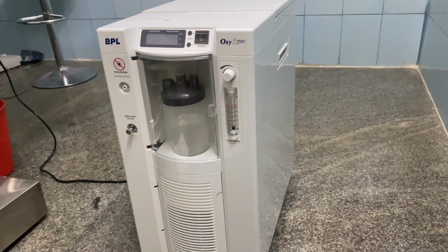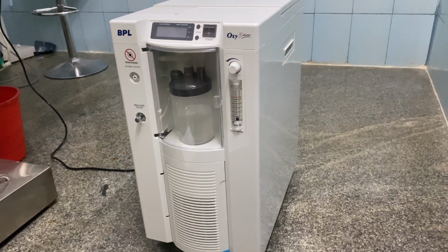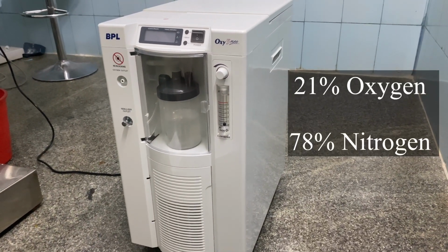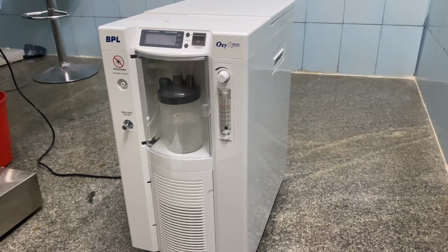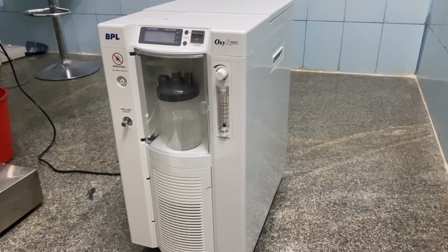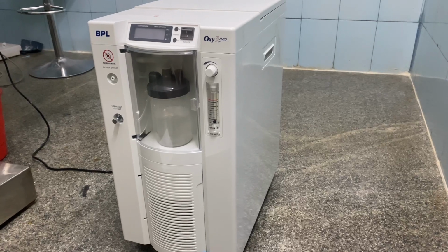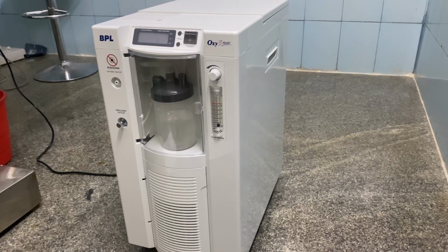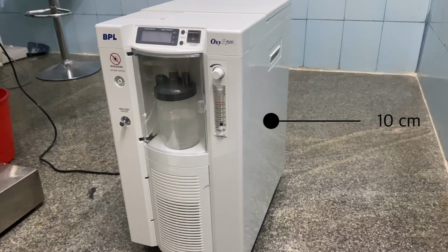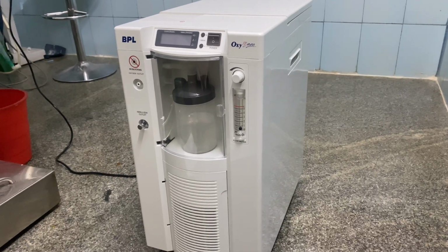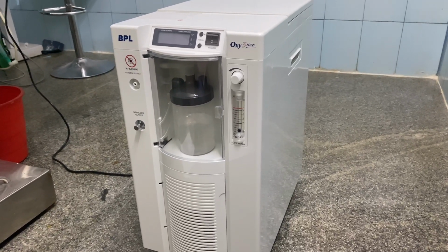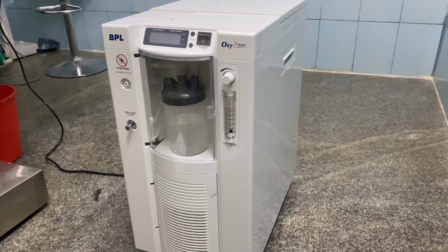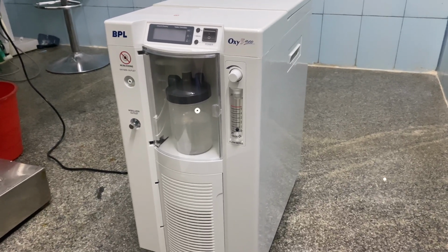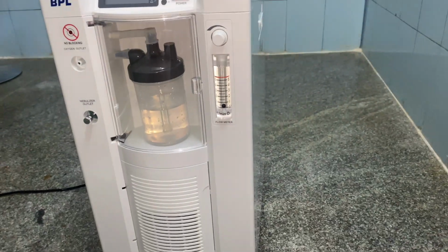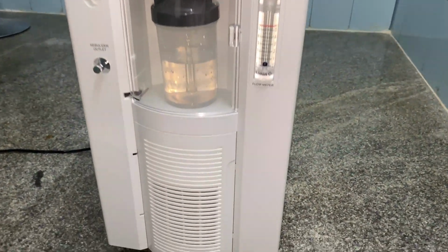In atmospheric air, 21% oxygen and 78% nitrogen will be there. This device removes the nitrogen and gives the oxygen-enriched gas to us. Keep the device at least 10 cm away from the furniture and other devices, and don't put the device very close to the wall. So at least a 10 cm gap has to be given, and don't cover this device with any cloth covers. Don't use this in a dusty atmosphere.